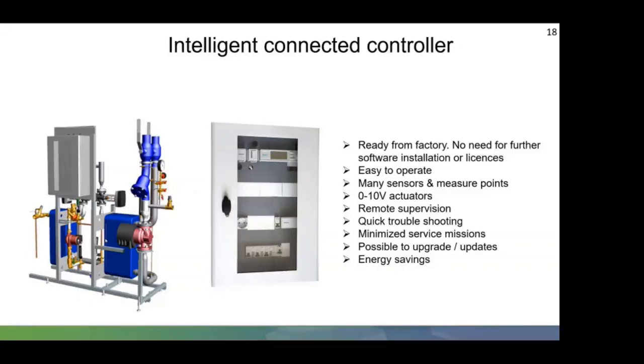So, intelligent connected controller. The correct design of a substation is very important, but equally good controls play a very large part in creating a highly efficient substation. I'm sure I read somewhere that the whole is greater than the sum of its parts. So again, it's making sure that whatever's been selected will work together. By implementing greater controls, we make the whole substation better.